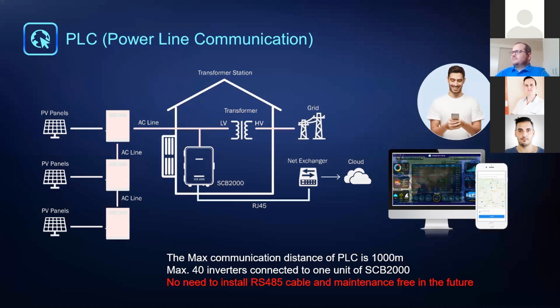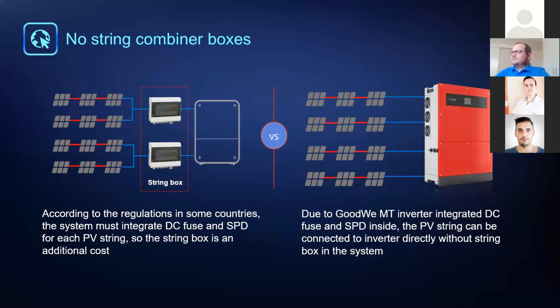Okay, so PLC. We have this option available with a maximum distance of 1,000 meters of cable run between all the inverters and the PV system as a whole. And then you can use this option with up to 40 inverters connected to our SCB2000. The SCB2000 is a product that enables PLC and is used to integrate the system using PLC. And also with multi-MPPTs, this reduces your need for string combiner boxes, which is another cost-saving factor. I won't go into too much detail there. I think it speaks for itself.